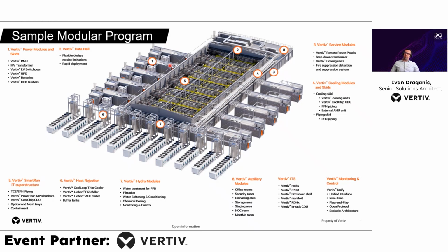On the outside, we have the power modules. This is number one. The power module is a combination of medium and low voltage power. It features a medium voltage ring main unit for the medium voltage distribution topology, the transformer from medium voltage to low voltage. And then on the low voltage side, we have the low voltage distribution panels, which feed the UPS. And from the UPS, we have the outgoing bus that feeds all the critical infrastructure in the white space and the cooling equipment as well. We have the batteries inside, the appropriate cooling, and all the BMS systems. So the power module comes to site as a single self-standing structure that is weatherproof and able to power the critical infrastructure.